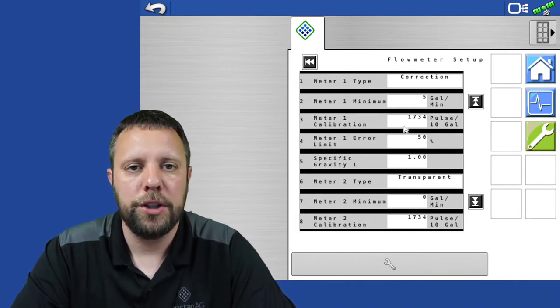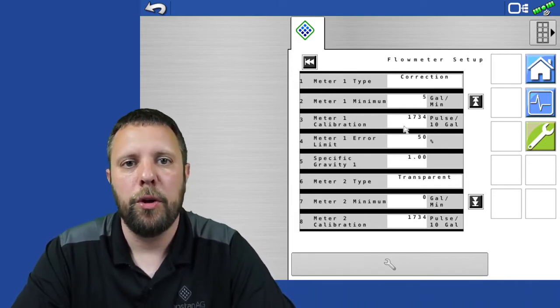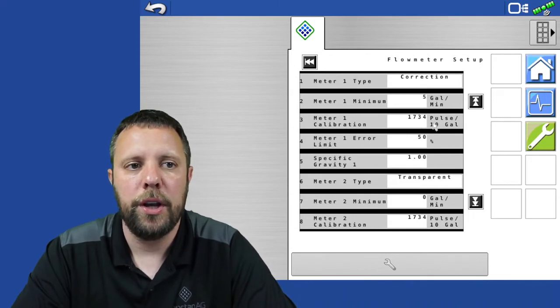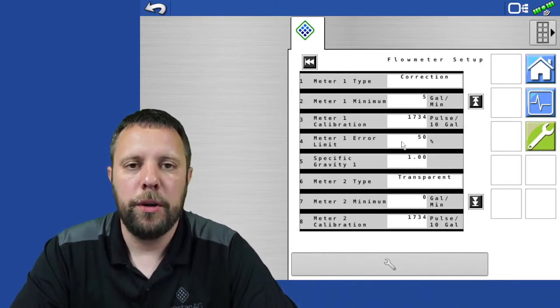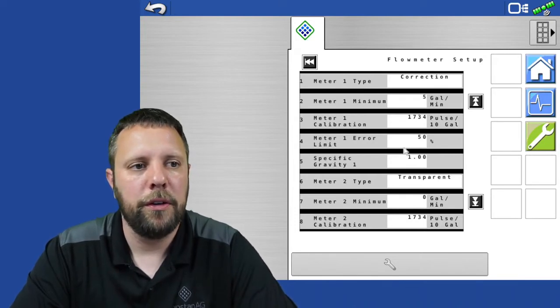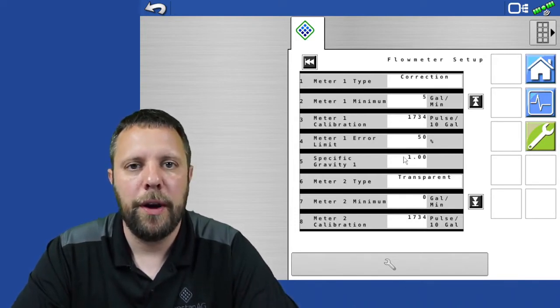Meter 1 calibration, you need to go find what's on your flow meter tag and enter that number in pulses per 10 gallons. Flow meter error limit, we just leave that set to 50%. Default, no need to change. Specific gravity, leave that at 1, no need to change.